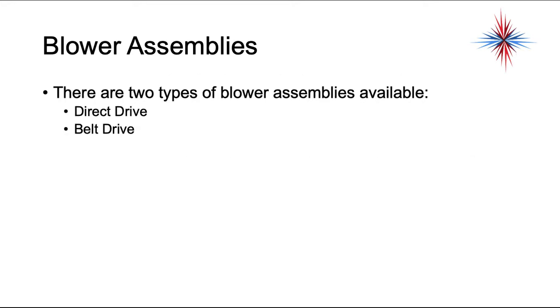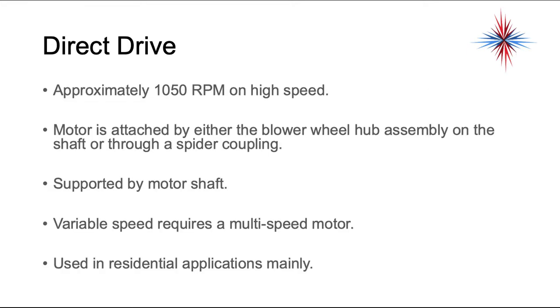There are two types of blower assemblies available: direct drive and belt drive. The direct drive has approximately 1050 RPM on high speed. The motor is attached by either the blower wheel hub assembly on the shaft or through a spider coupling. The motor is actually supported by the motor shaft and the blower wheel. The variable speed requires a multi-speed motor and it's used in residential and light commercial applications.